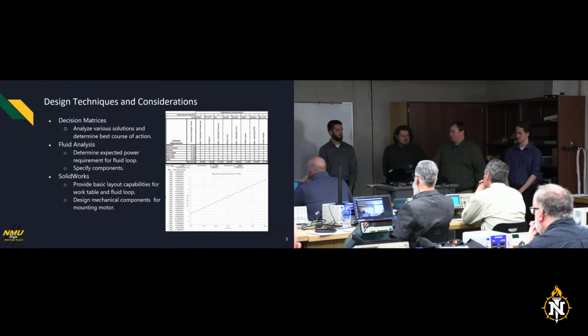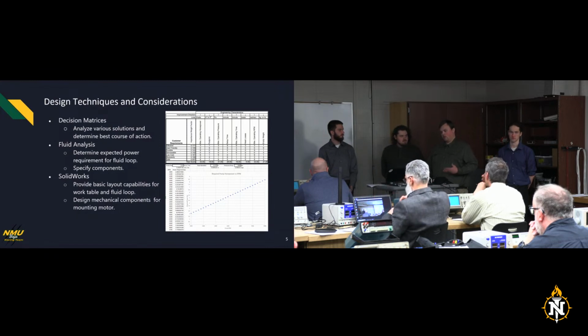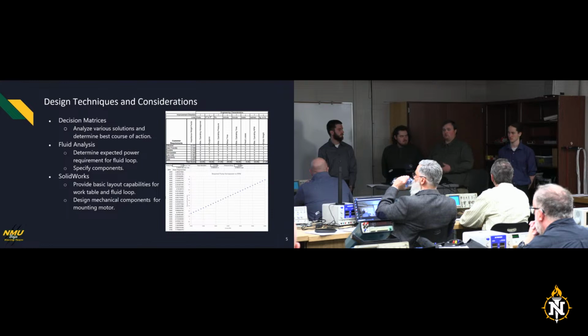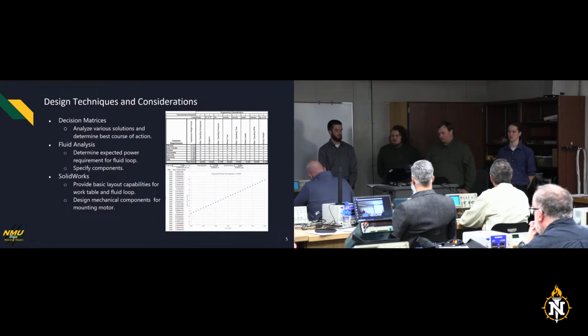Component selection, I would say. We had sort of two trains of thought at the beginning of this project. One consideration we made is that if you have a pump that only requires 1 horsepower and a 10 horsepower motor, you're never going to properly load that motor. But at the same time, we were also thinking that technically it shouldn't matter if we can close the fluid loop and build a sufficient amount of pressure, then it should still load the motor. That turned out not to be the case, as when we did that with the electric motor specifically, the electric motor did not care, and it just overpowered the pump and started skipping the belt off, so it was a pretty interesting system failure. Thankfully, no damage to anything, but it was a fun test, I'll say.